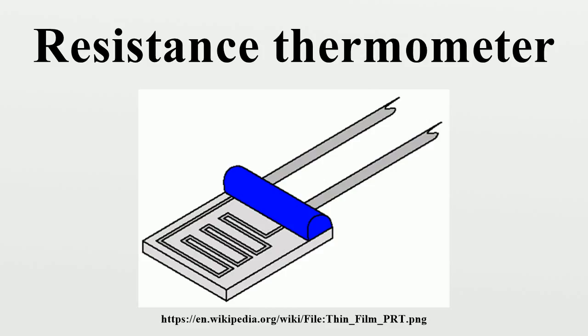Stability. Ability to maintain R versus T over time as a result of thermal exposure. Repeatability. Ability to maintain R versus T under the same conditions after experiencing thermal cycling throughout a specified temperature range. Hysteresis. Change in the characteristics of the materials from which the RTD is built due to exposures to varying temperatures. Stem conduction. Error that results from the PRT sheath conducting heat into or out of the process. Calibration, interpolation. Errors that occur due to calibration uncertainty at the cal points, or between cal points due to propagation of uncertainty or curve fit errors.